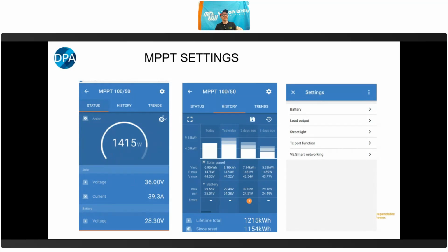But if you see it's never getting anywhere near that Pmax value of the rating of the panel - say it's a 1.5 kilowatt array, but our Pmax value is only 200 watts - that might mean you've got some shade on the solar panels or something like that, because it's never putting its maximum wattage out at all during the day.